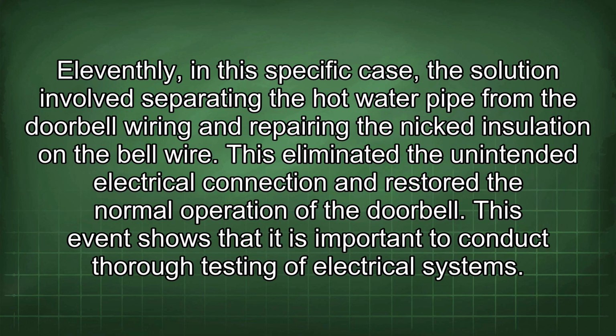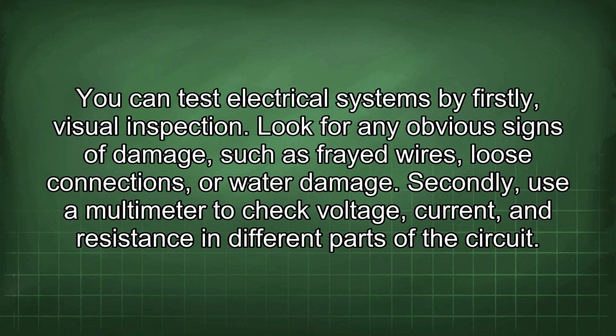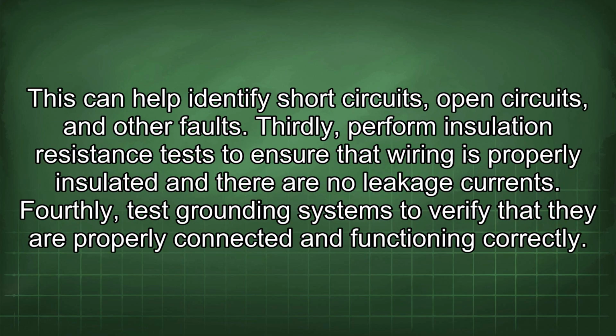Eleventhly, in this specific case, the solution involves separating the hot water pipe from the doorbell wiring and repairing the nicked insulation on the bell wire. This eliminated the unintended electrical connection and restored the normal operation of the doorbell. This event shows that it is important to conduct thorough testing of electrical systems. You can test electrical systems by, firstly, visual inspection. Look for any obvious signs of damage, such as frayed wires, loose connections, or water damage. Secondly, use a multimeter to check voltage, current, and resistance in different parts of the circuit. This can help identify short circuits, open circuits, and other faults.